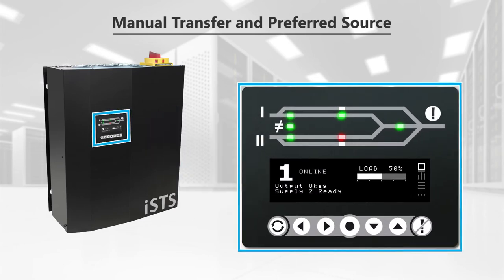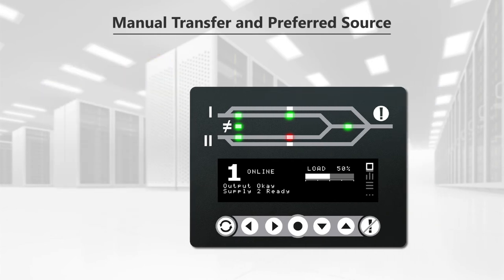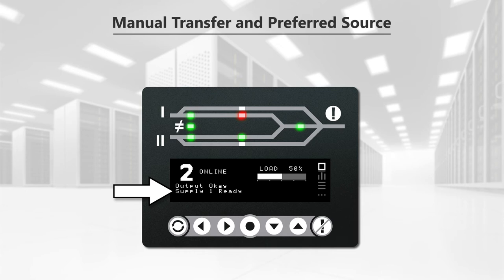Conveniently perform manual transfers and set a preferred source using the preferred source selection button on the user interface. Set the preferred as Source 1, Source 2, or no preference. The STS will default to the preferred source when it again becomes available.